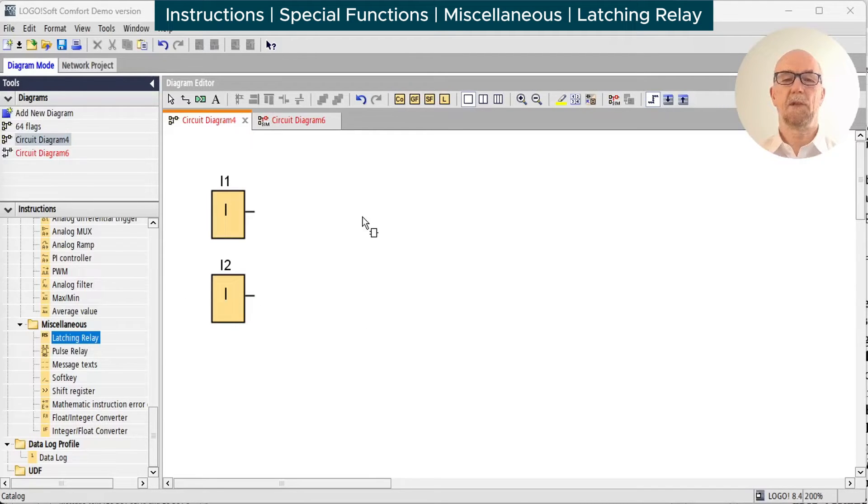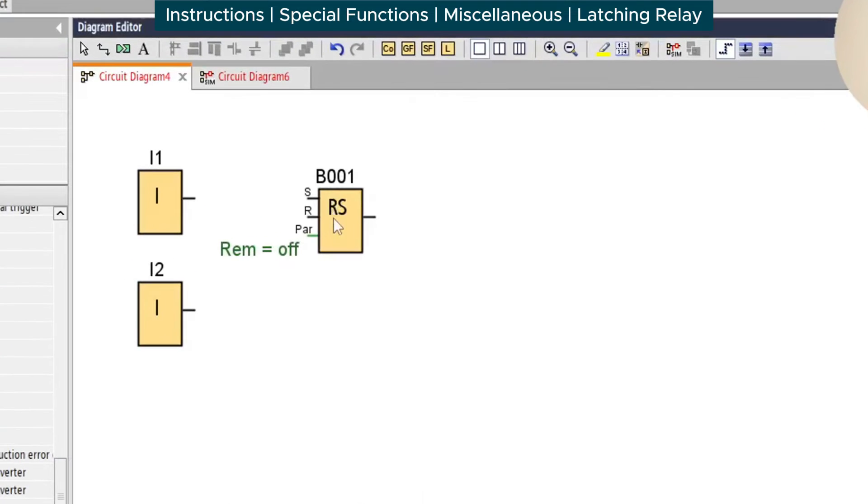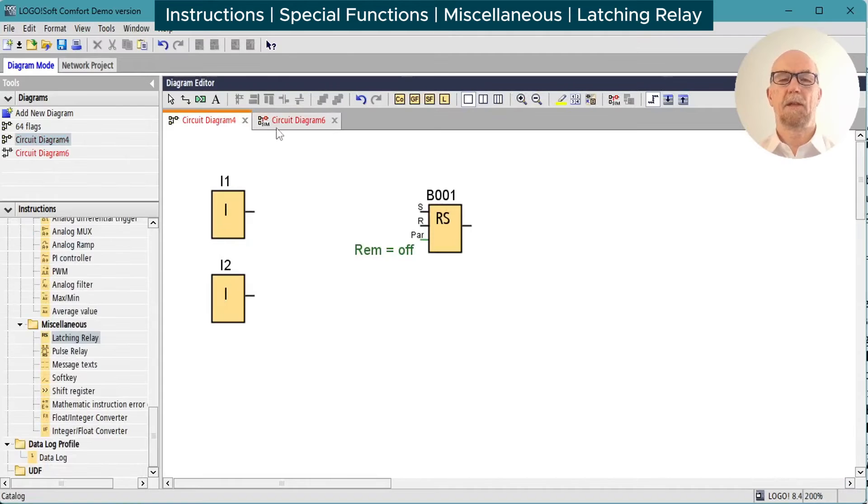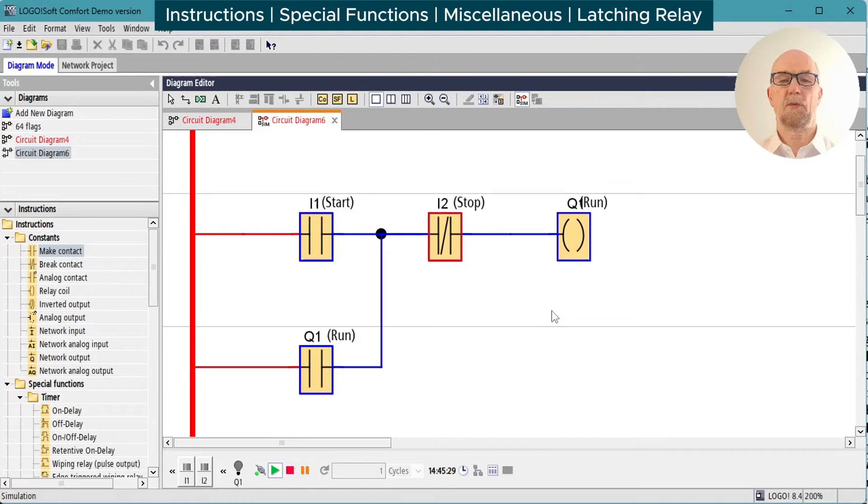The latching relay is a common control requirement. Traditionally in ladder logic, we would make a latching relay using a regular relay coil and one of its own contacts, so that when the start button is pressed, the relay turns on and holds itself on after the start button is released. Pressing the stop button interrupts the supply to the run relay, which opens this contact, unlatches, and the circuit is reset.